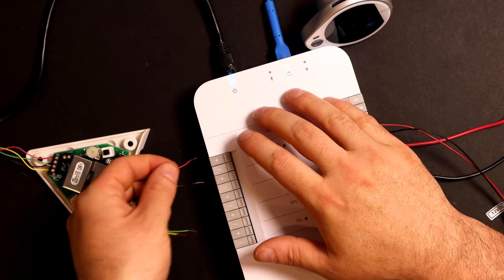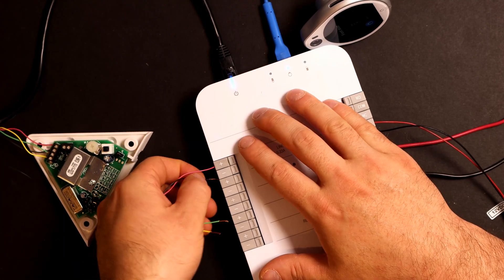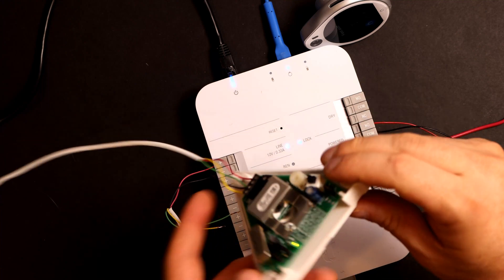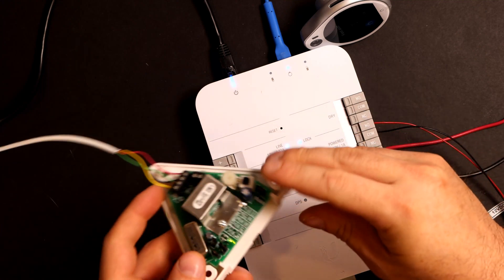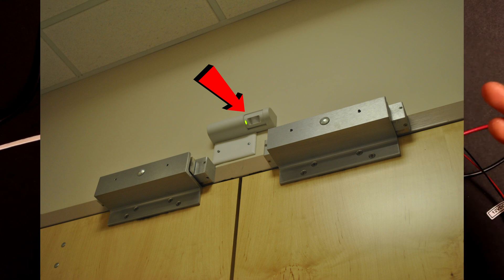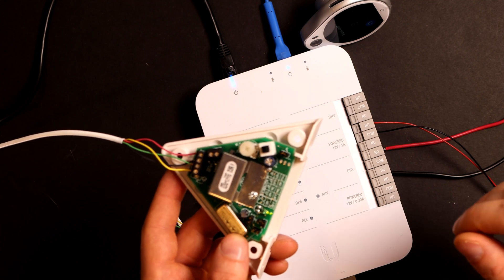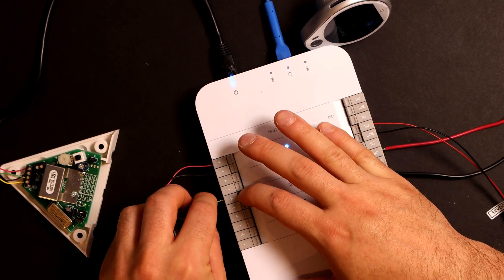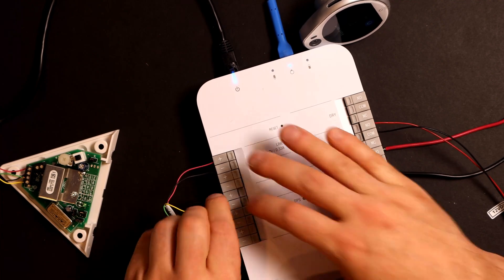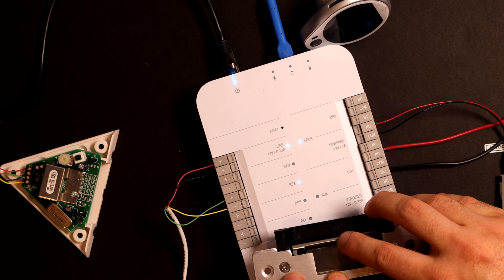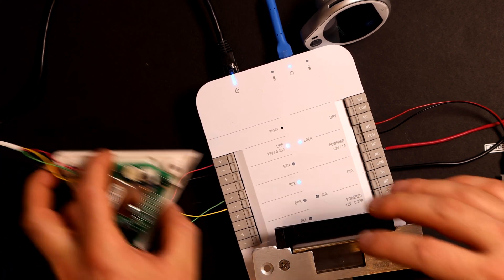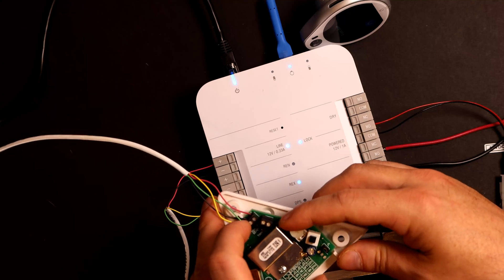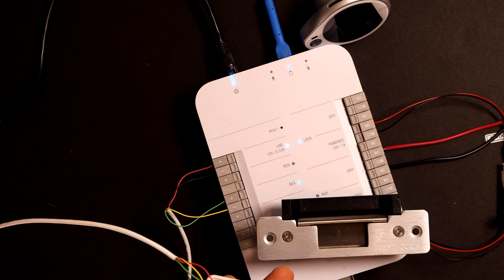I'm going to grab the positive of my power, and then I'll grab my negative. And here a little green light came on, and we have the motion sensor right inside. Usually you would see these above the door, so when you're walking towards the door, it just opens up the door for you, and you don't need to take any action. Now we need to grab our yellow and our green wire and put it in our request to exit. So the sensitivity on this thing is super high, so as I'm moving, the door lock is always open. But we can change that if we'd like. So they have this delay button, we just need to turn it. So now if I wave my hand in front of it, it will unlock. And we can see that the door is unlocked.